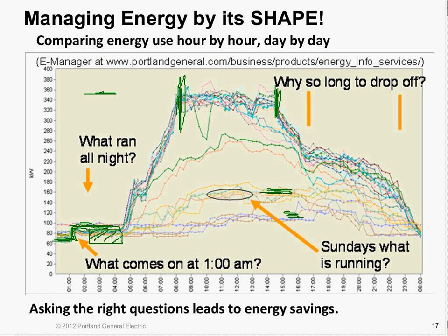Well, that's great for them, but the energy use is pretty dramatic out here. So they made a deal with the janitorial service to turn all the lights off and only have the lights on in the room that they were actually cleaning. They changed this shape to look a lot more like, get a different drawing tool here. Now the shape suddenly was way down here.